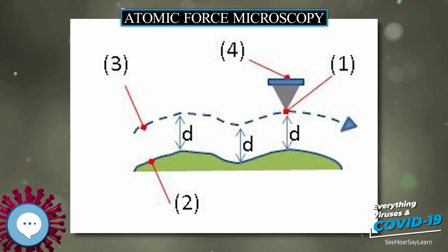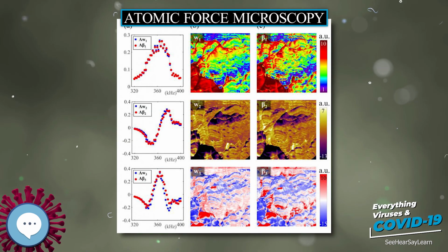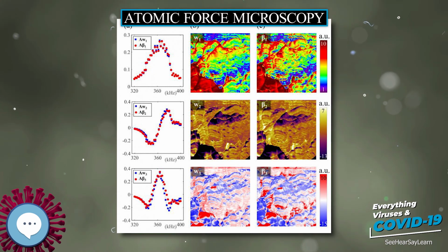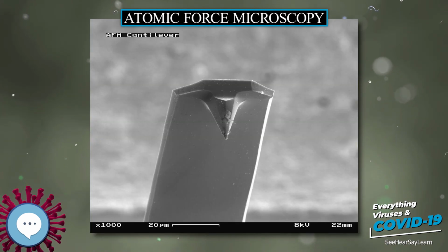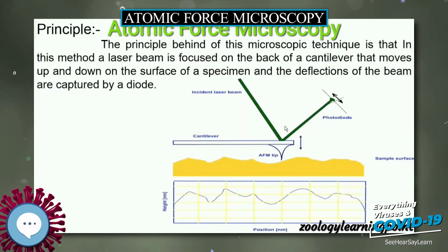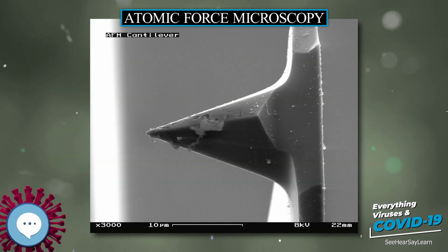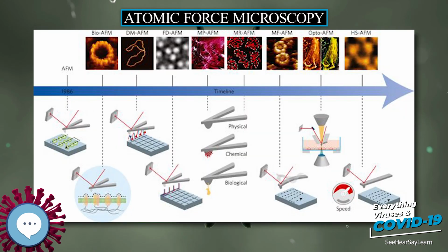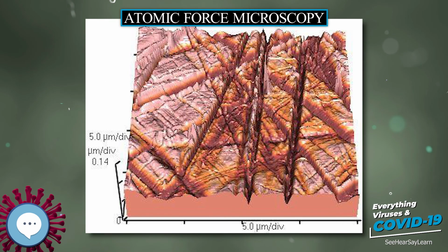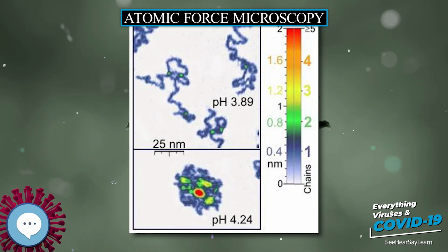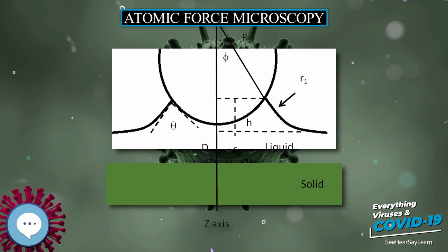Imaging modes. AFM operation is usually described as one of three modes, according to the nature of the tip motion: contact mode, also called static mode, as opposed to the other two modes, which are called dynamic modes: tapping mode, also called intermittent contact, AC mode, or vibrating mode, or, after the detection mechanism, amplitude modulation AFM; and non-contact mode, or, again after the detection mechanism, frequency modulation AFM. Despite the nomenclature, repulsive contact can occur or be avoided both in amplitude modulation AFM and frequency modulation AFM, depending on the settings.